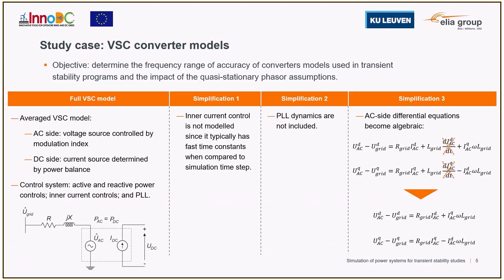The first simplification is where the inner current control is not modeled, since it tends to be a fast control and its time constants are small compared to the simulation time step. For the second simplification, the PLL dynamics is not included. And in the third simplification, the derivatives associated with the AC side differential equations are neglected, turning them into algebraic equations.